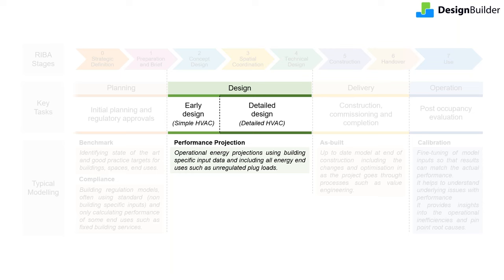In early stages, simulation can be used to test and refine operational energy targets under a range of real-world scenarios using initial performance models with simple HVAC. As design progresses, areas where detailed HVAC modeling is particularly beneficial include: greater ability to optimize air-side modeling of mechanical ventilation systems, water-side modeling of heating and cooling systems including heat recovery, simulation of heating and cooling plant, fan, pump, and equipment performance in more detail, plus testing of various control options.